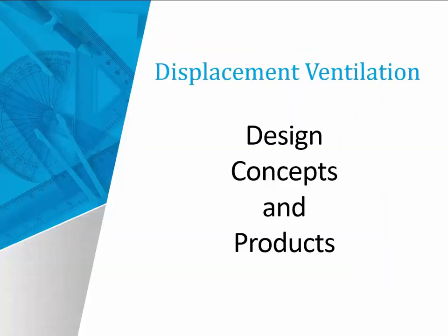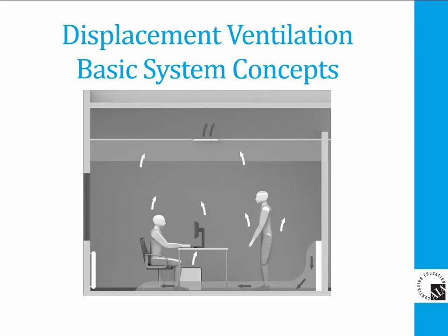Now let's look at Displacement Ventilation. Displacement ventilation is a fully stratified comfort conditioning system that has become a popular solution to handle spaces where ventilation effectiveness and quiet solutions are desired. Cool air is introduced at low levels near or at the floor, discharged horizontally across the floor at low velocity, usually less than 100 feet per minute, until a heat source is reached. Cool air will mix with the heat and stratify upward until it reaches the return height.